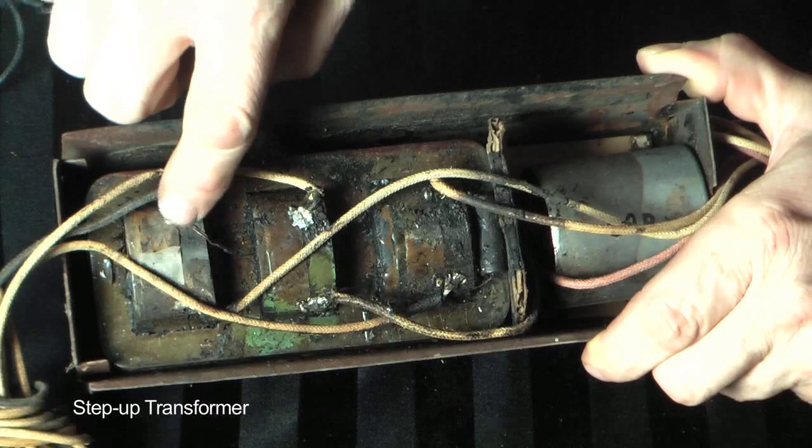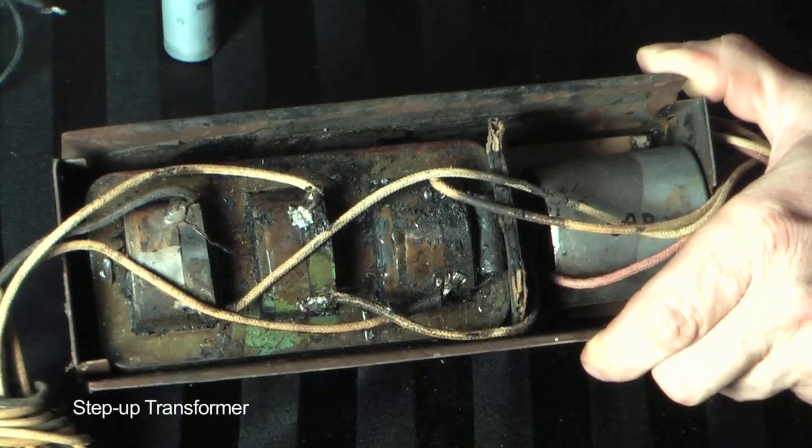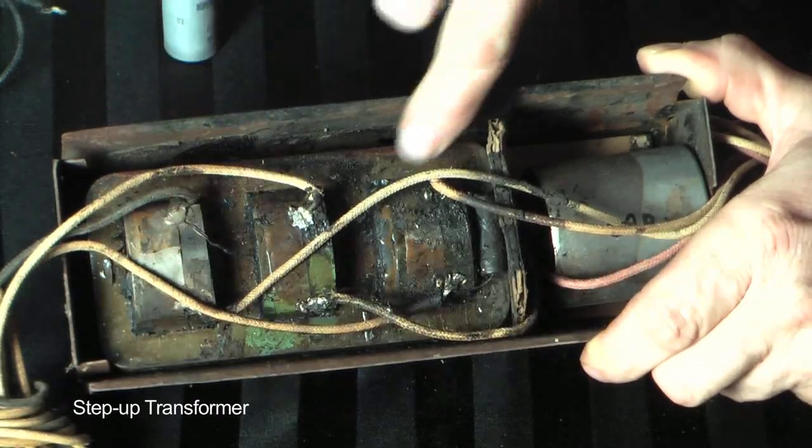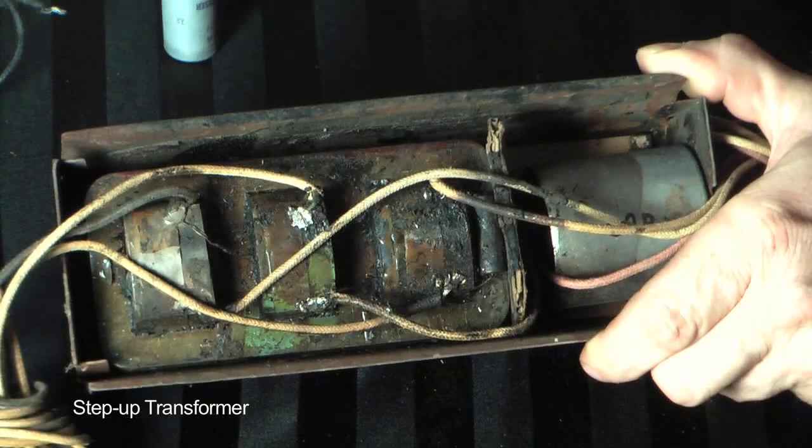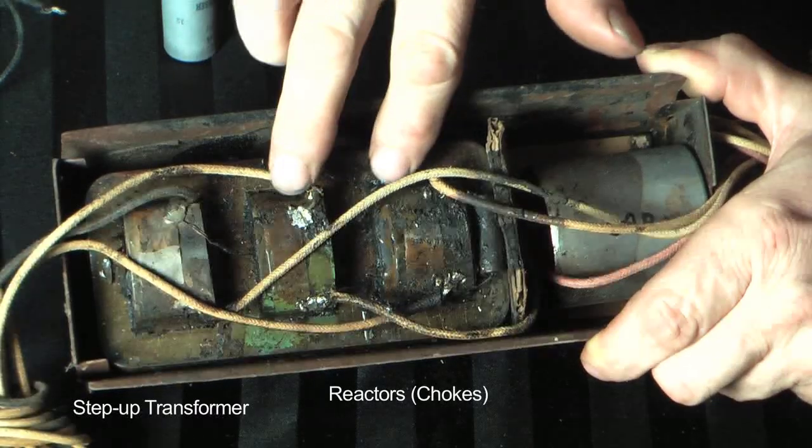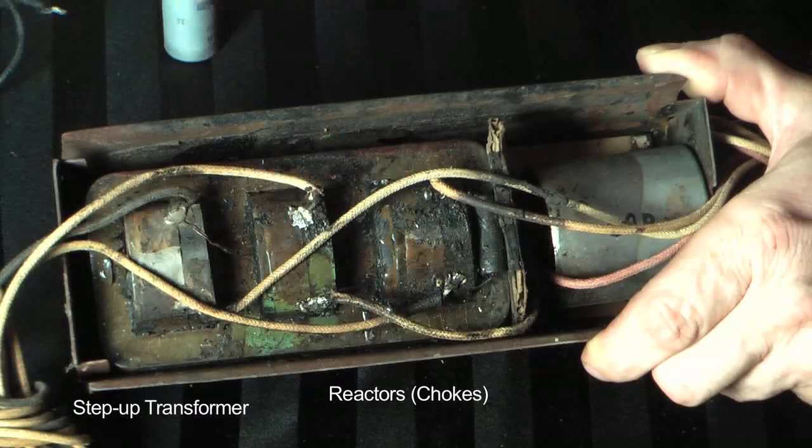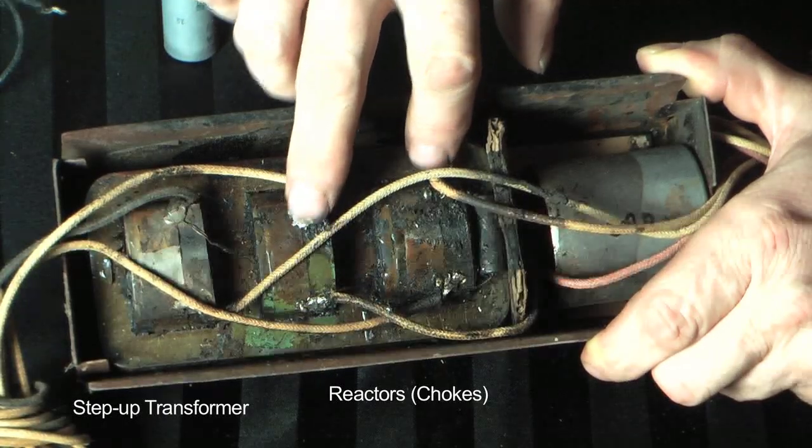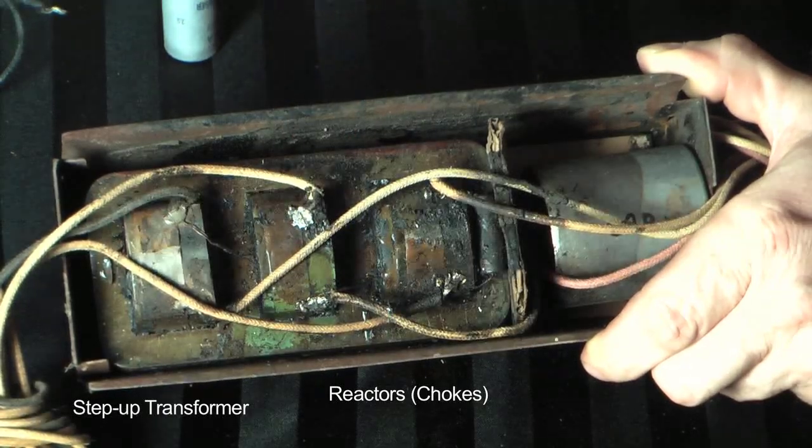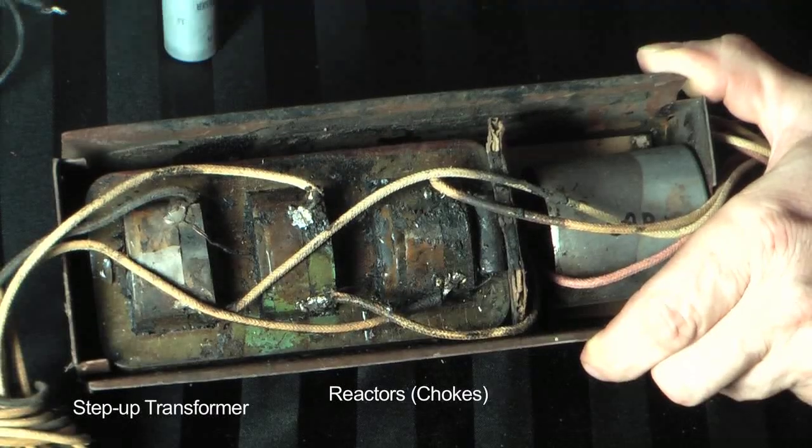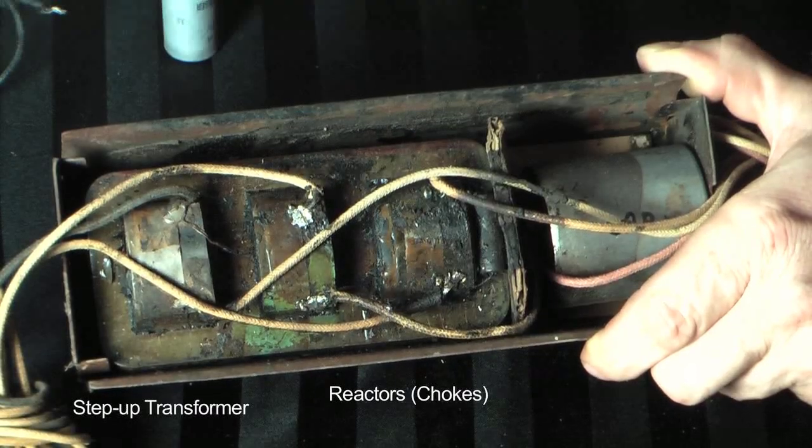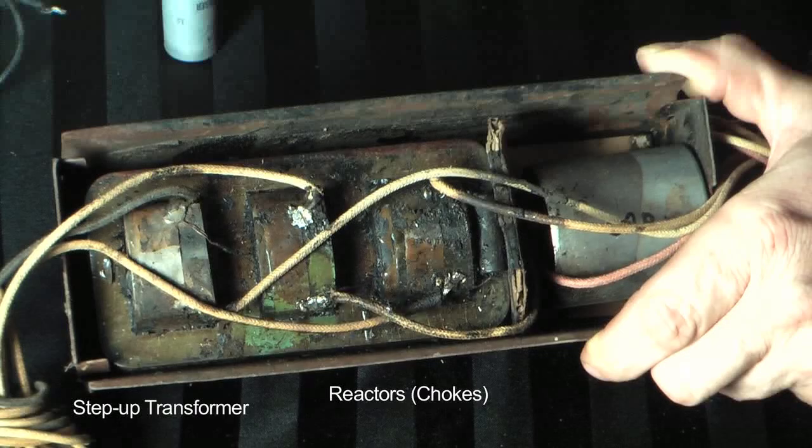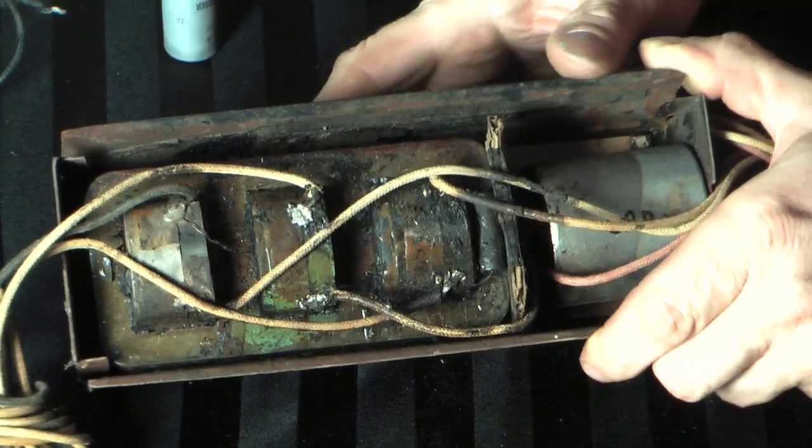Then you have two reactors, one for each lamp. That's what actually limits the current to the lamps so they can't get too much current. They're called chokes. And then there's a third winding called a starting compensator, which I won't go into right now. And that's necessary for starting of one of the two lamps.